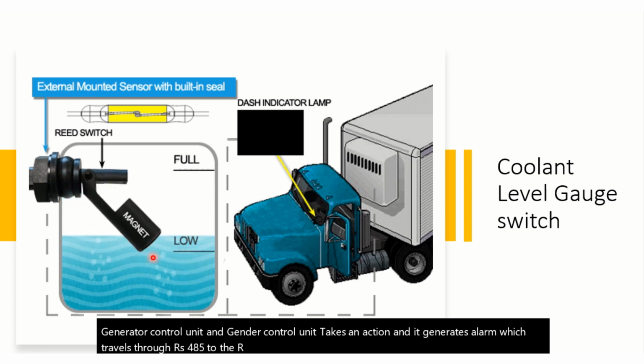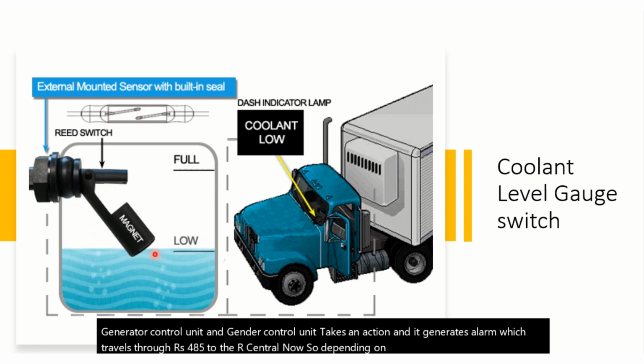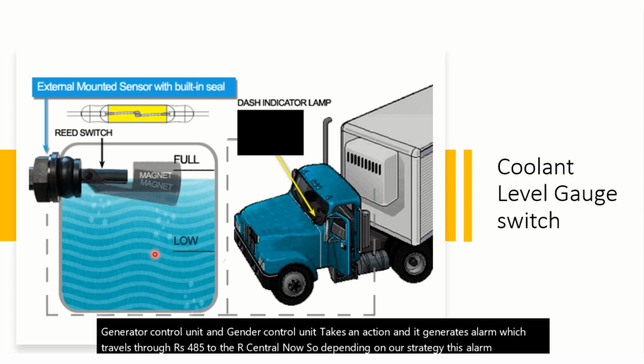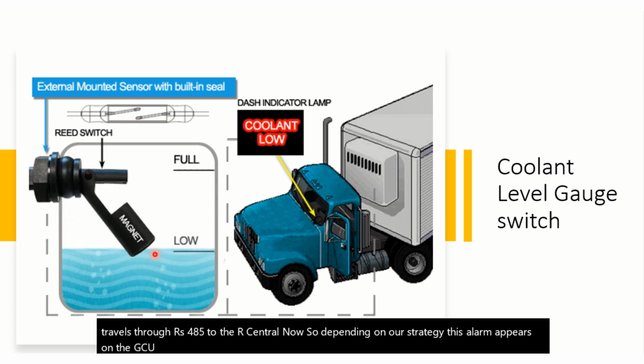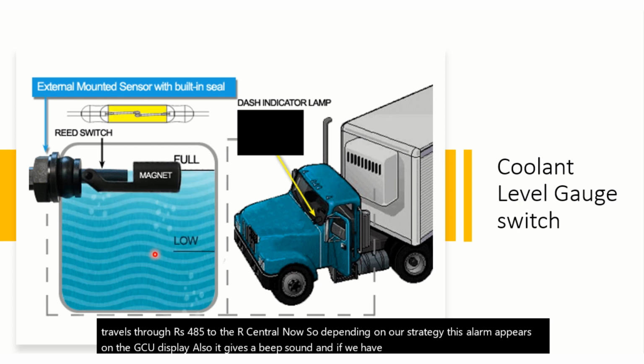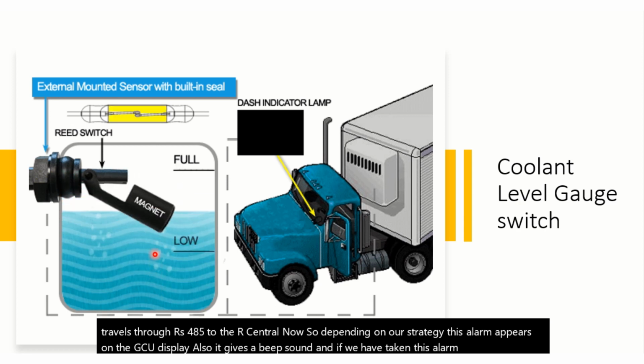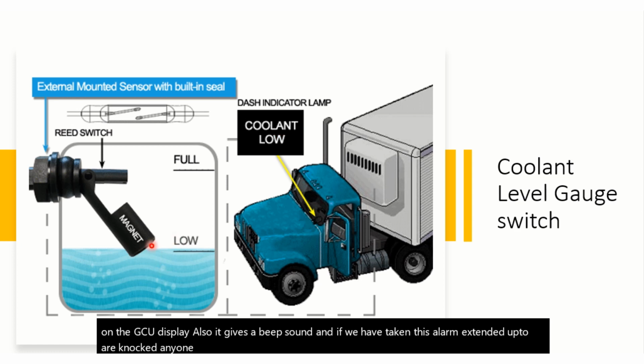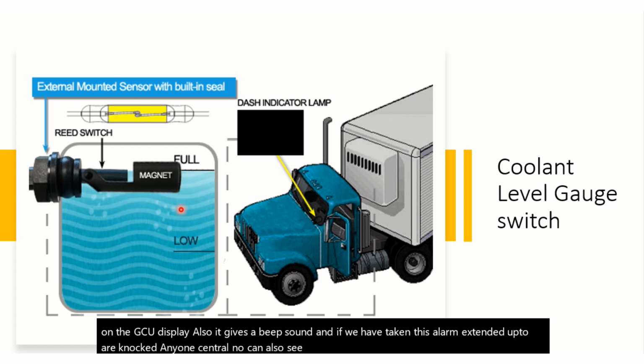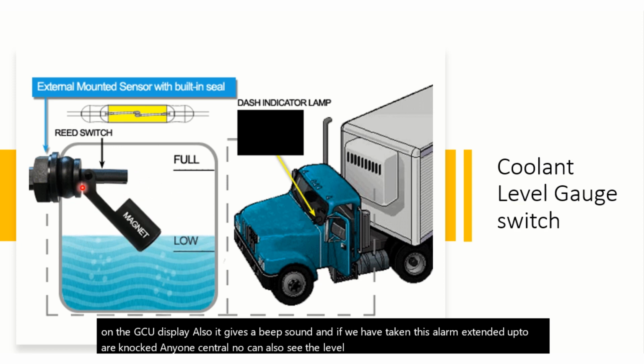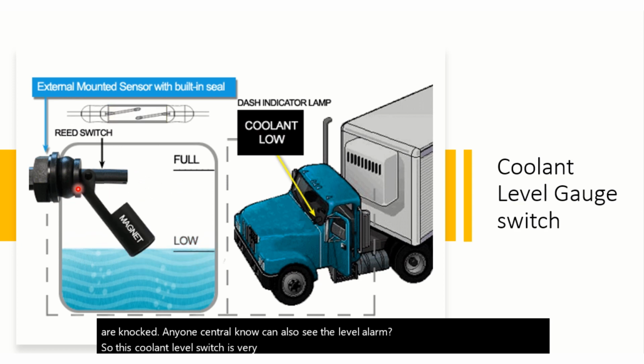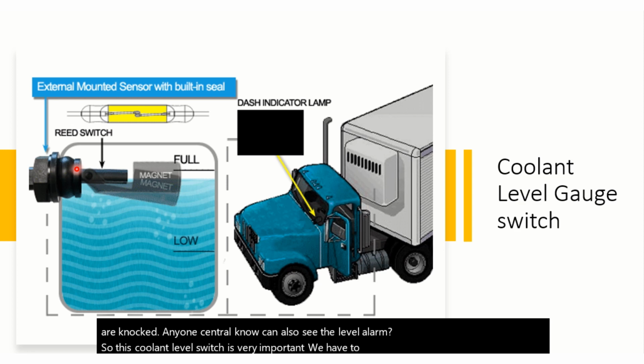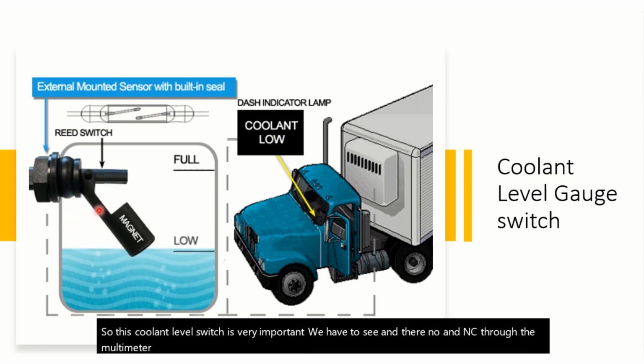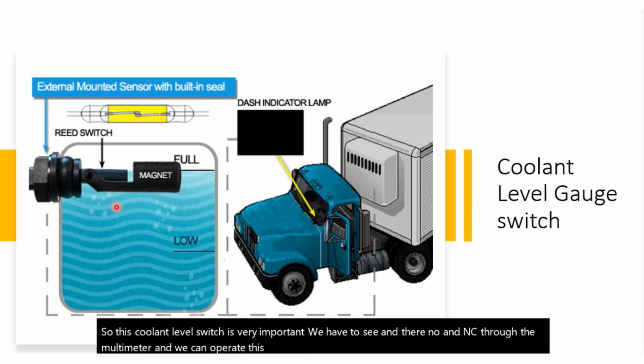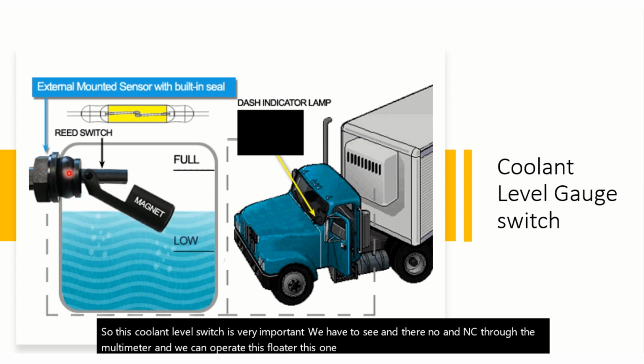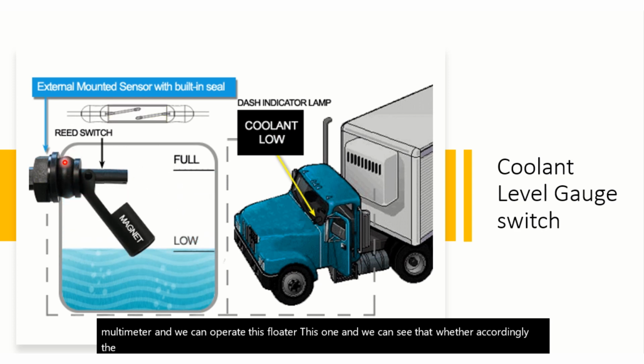Depending on our strategy, this alarm appears on the GCU display. It also gives a beep sound, and if we have extended this alarm up to our knob, then even the central knob can see the level alarm. So this coolant level switch is very important. We have to check its NO and NC through the multimeter, and we can operate the float and see whether the NO/NC is changing accordingly or not.